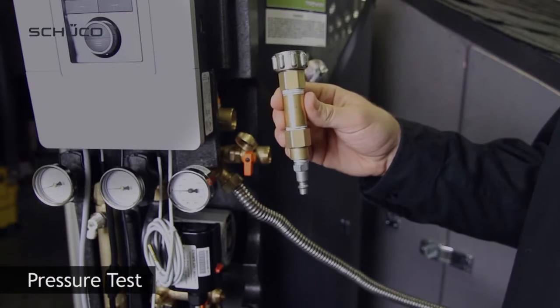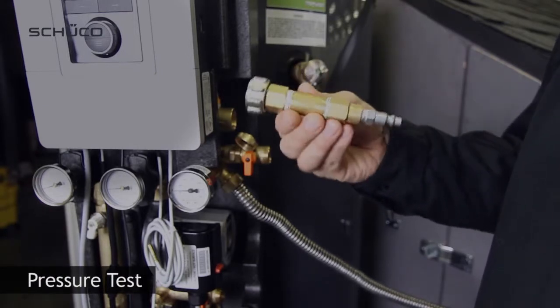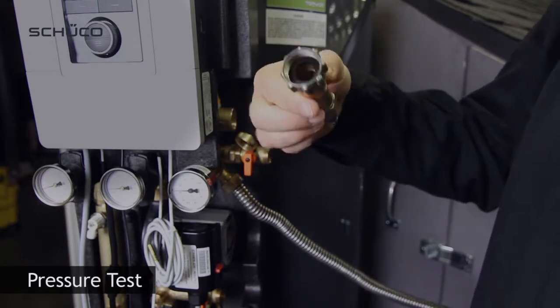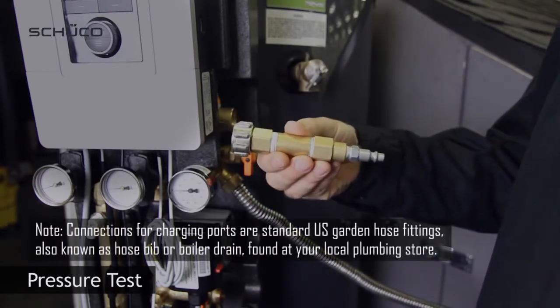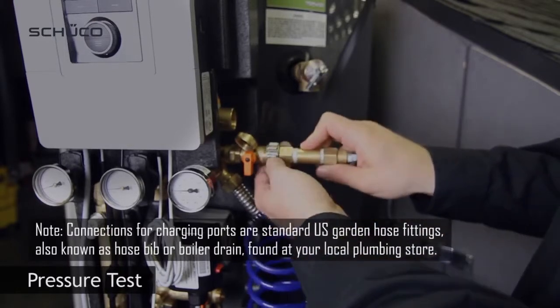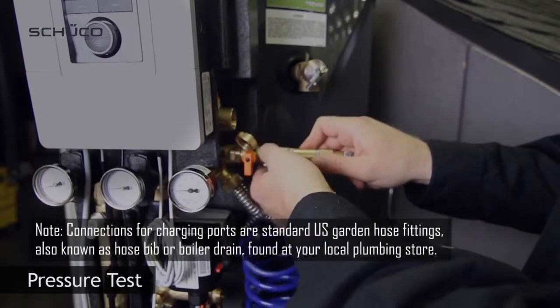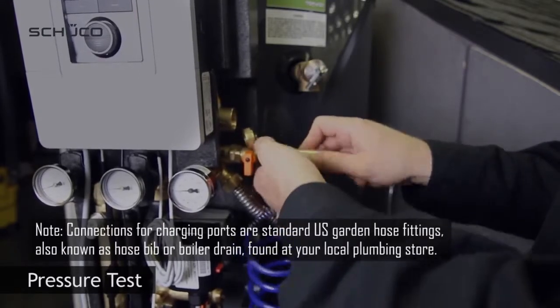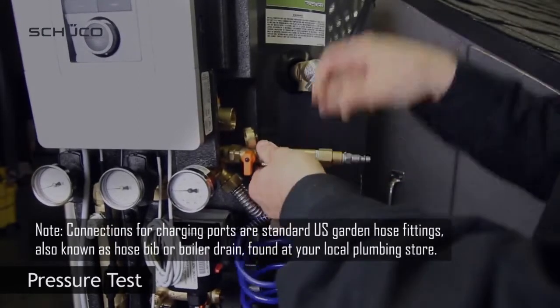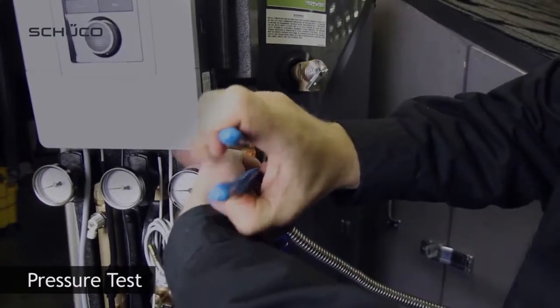In order to pressure test the loop with air, you will need to build your own adapter device to connect to the solar station. This device will connect to the charging port using a 3/4 inch GHT fitting. Fasten the device hand tight, then use channel locks to properly seal.